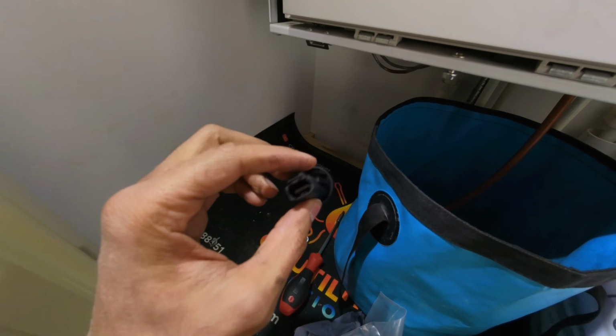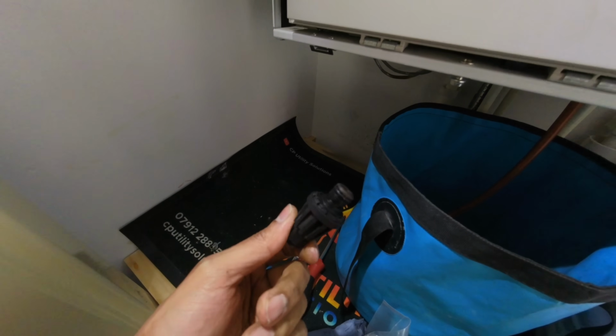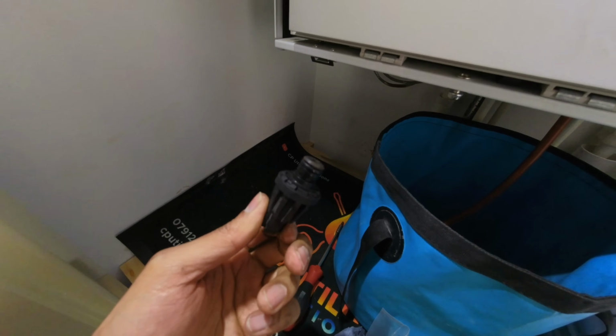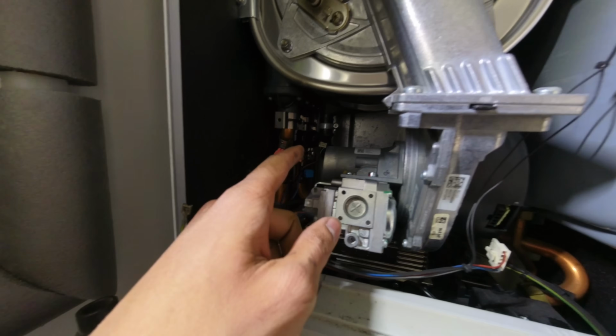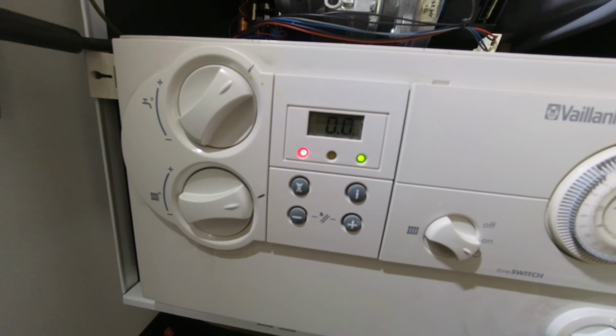So I tried to clean out the old pressure sensor, but it wasn't happening, I was still getting 0.3 of a bar reading on it. So pop the new one in, and now we've got 0, that's what it should be reading. I didn't want to risk getting a call back later on with F75 issues. Just change it, I'll sort out the price afterwards.